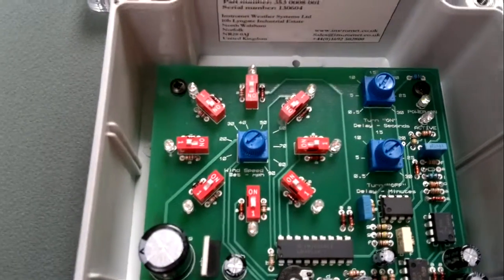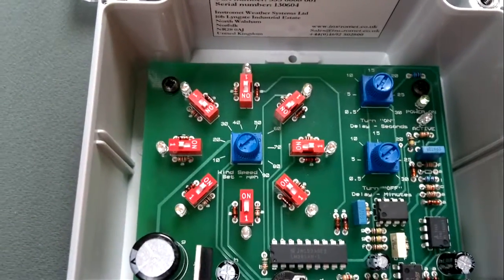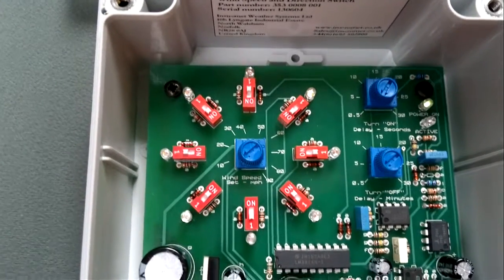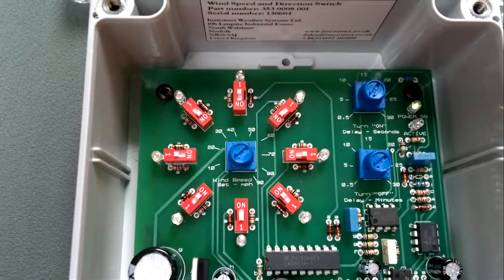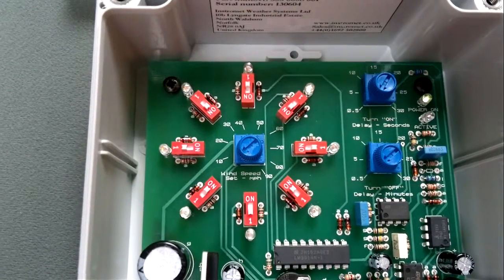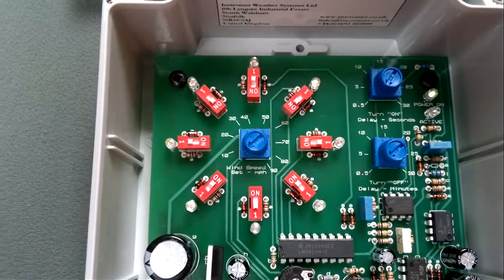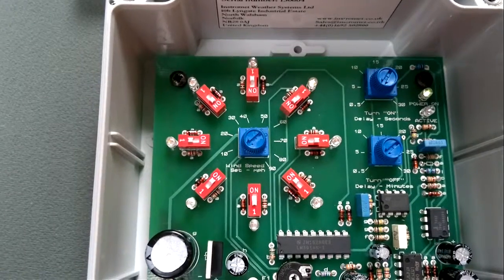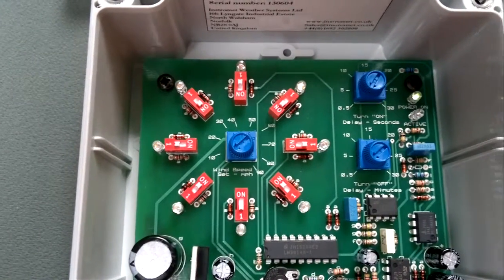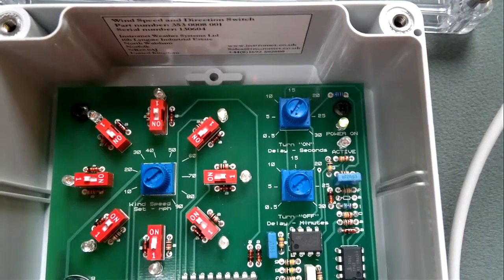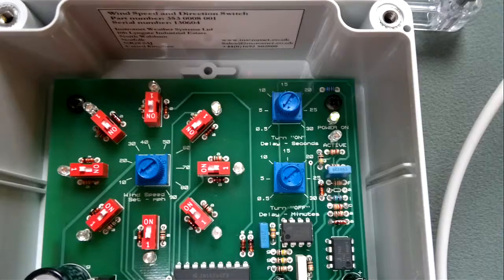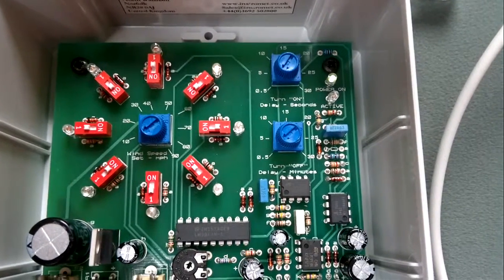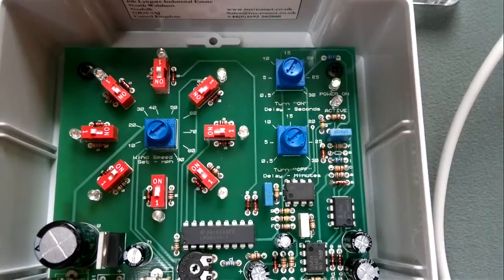Then at the back of the PCB we have the selection switches there for the wind direction. Plus there are indicating lights showing you which direction is active at the moment. In the middle there is the wind speed selection potentiometer. As you see that ranges from 0 to 90 miles per hour. Then at the back we have an on delay to prevent the unit from activating from short gusts of wind, and then an off timer to make sure the unit stays on for as long as it is required.